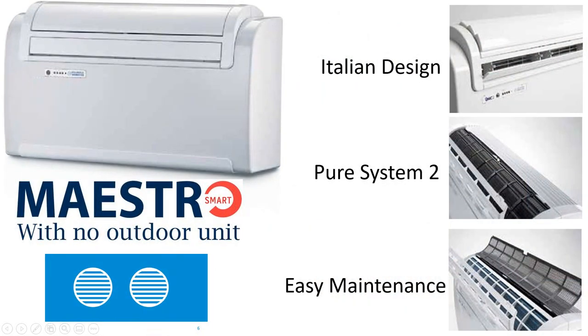So again, Italian design, they use what they call the Pure System 2. There's three different filters that can be used, and it's very easy maintenance. So if you look at the design here of the unit, you can see it's very low profile. It doesn't come out from the wall too far, but this is a completely self-contained unit right in this area right here. Can you see my cursor moving? Yes. Okay, so right in this area here is where the compressor is, but when you hear this unit running, you cannot hear the compressor even if you put your ear next to it, okay? This unit is as quiet as an air handler for a mini split, and it has the compressor and condenser fan located inside of it, so that's rather impressive.